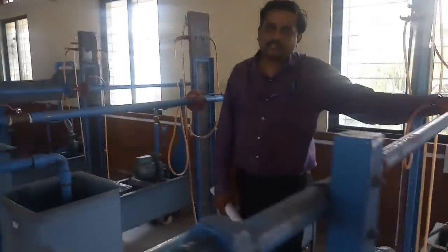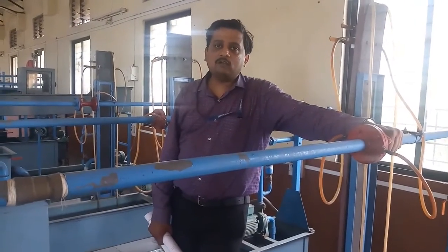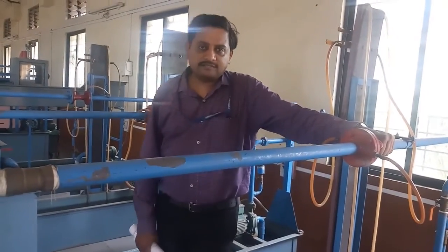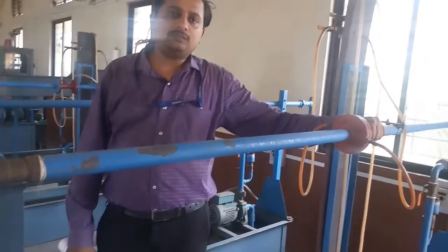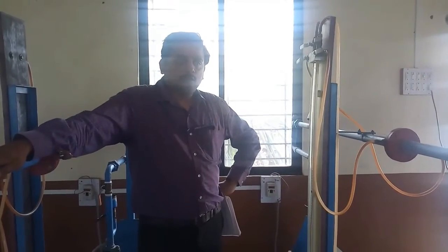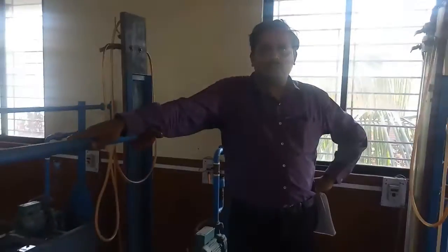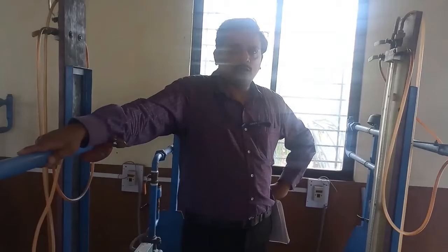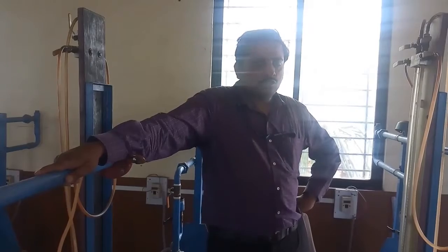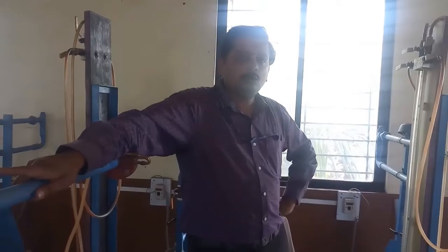So what's the aim of this experiment? The aim of the experiment is to find out the CD value, or you can say it's a verification of the CD itself. So what we are doing here is finding the CD value, or you are verifying, or you can say you are calibrating the orifice meter. You can use either word: either calibration, or finding the CD value. The CD value here lies between 0.6 and 0.65. So how to conduct this experiment?